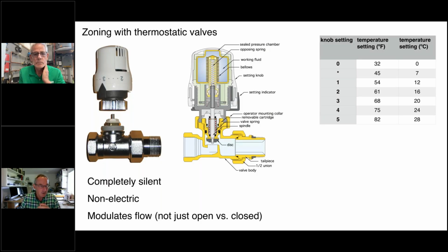One of the things that is characteristic of these types of valves from just about anybody that makes them, you'll see numbers like 1, 2, 3, and so forth on the actuator, not temperatures. And that's done for a number of reasons. One is you don't have to worry about the difference between a valve calibrated in Fahrenheit versus Celsius. And secondly, this encourages people to set the valve to a condition where they're comfortable in the room, not having to know what that temperature is. You don't have to know that it's either 68 or 70 or 72 degrees Fahrenheit to know if you're comfortable.